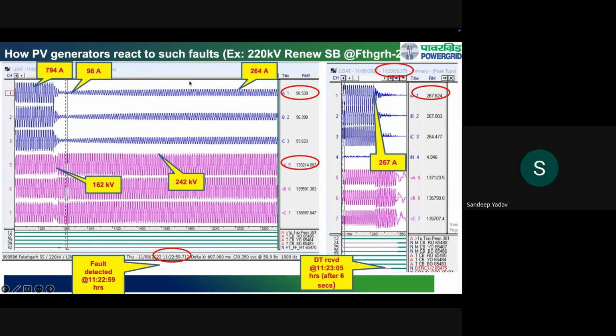Now, let's take a look at the fault ride-through behavior of the inverters. The initial 3 channels are the R, Y, B phase currents, and the bottom 3 channels are the R, Y, B phase voltages. In the pre-fault, the current was normal, about 794 ampere, and the voltage was also normal.